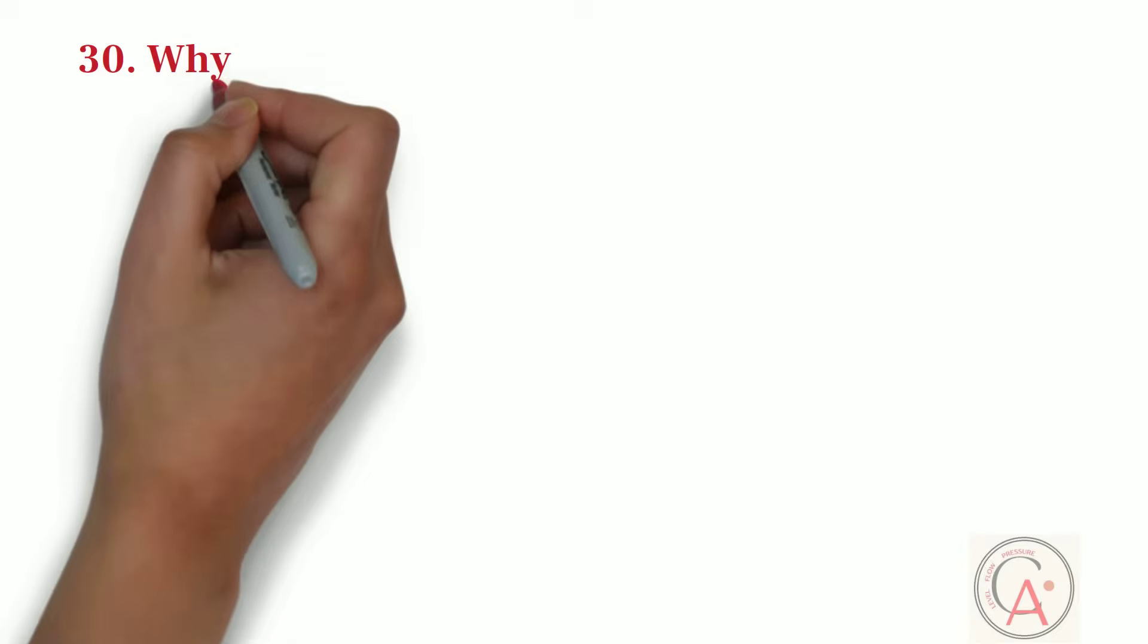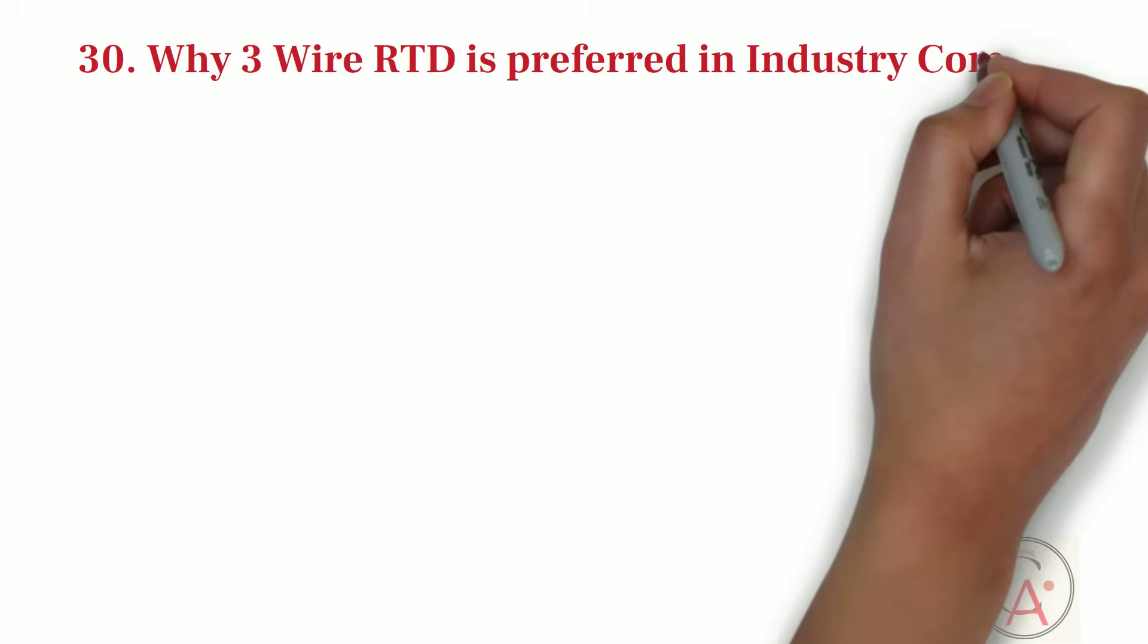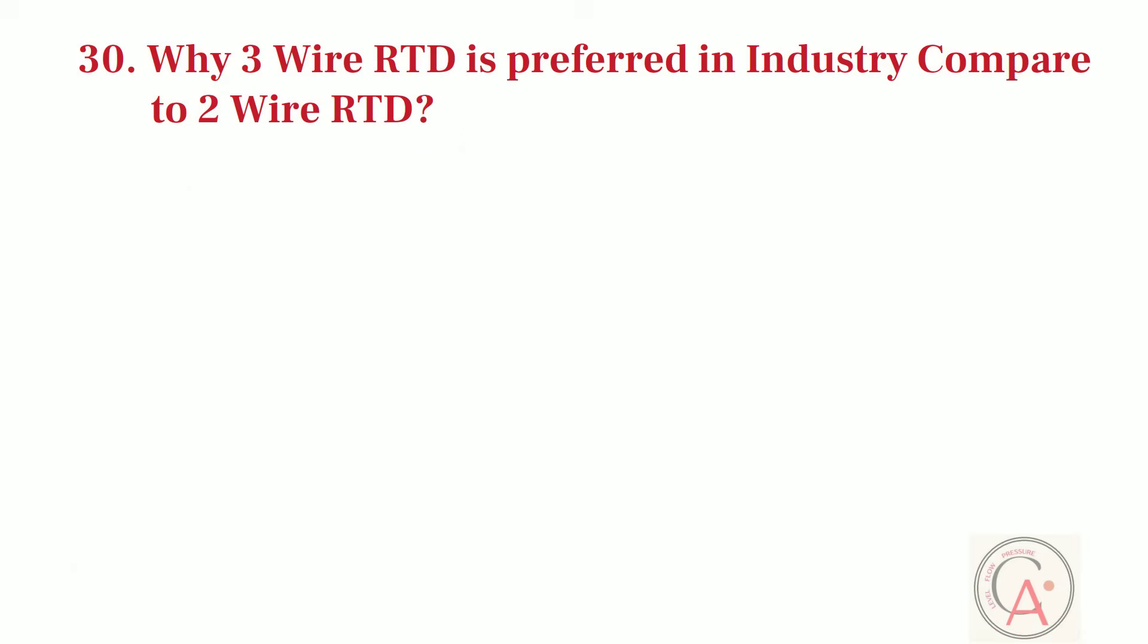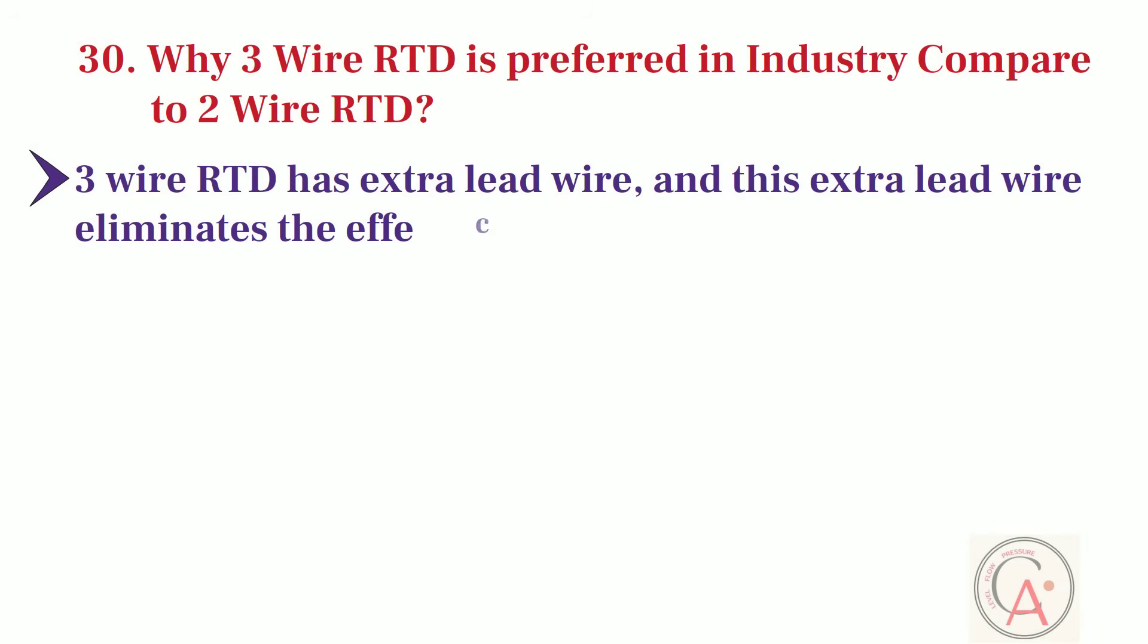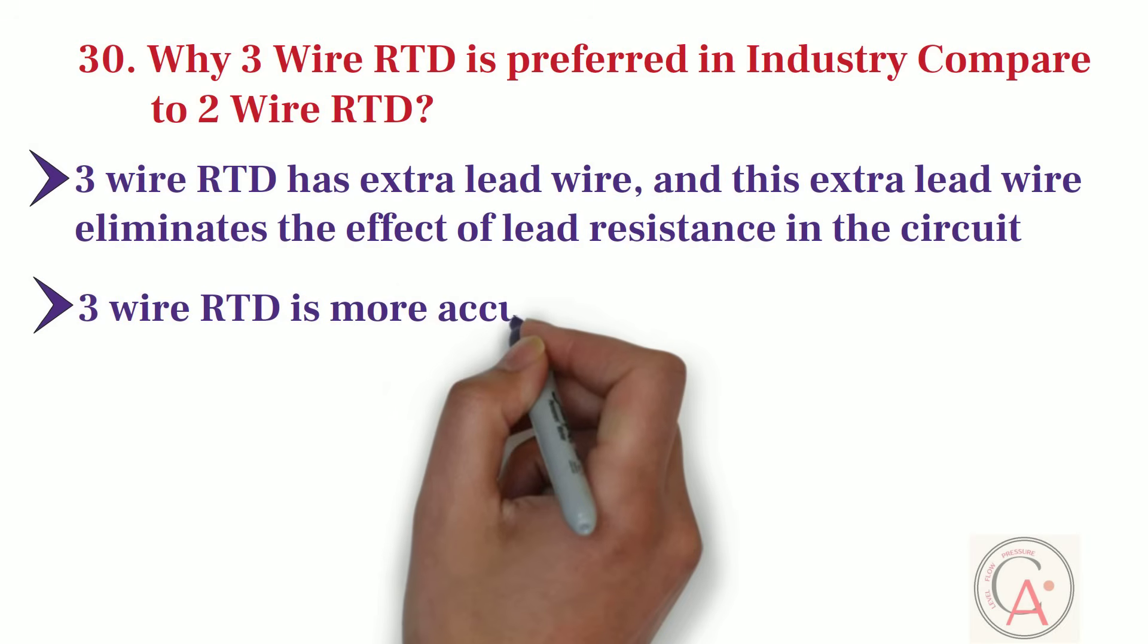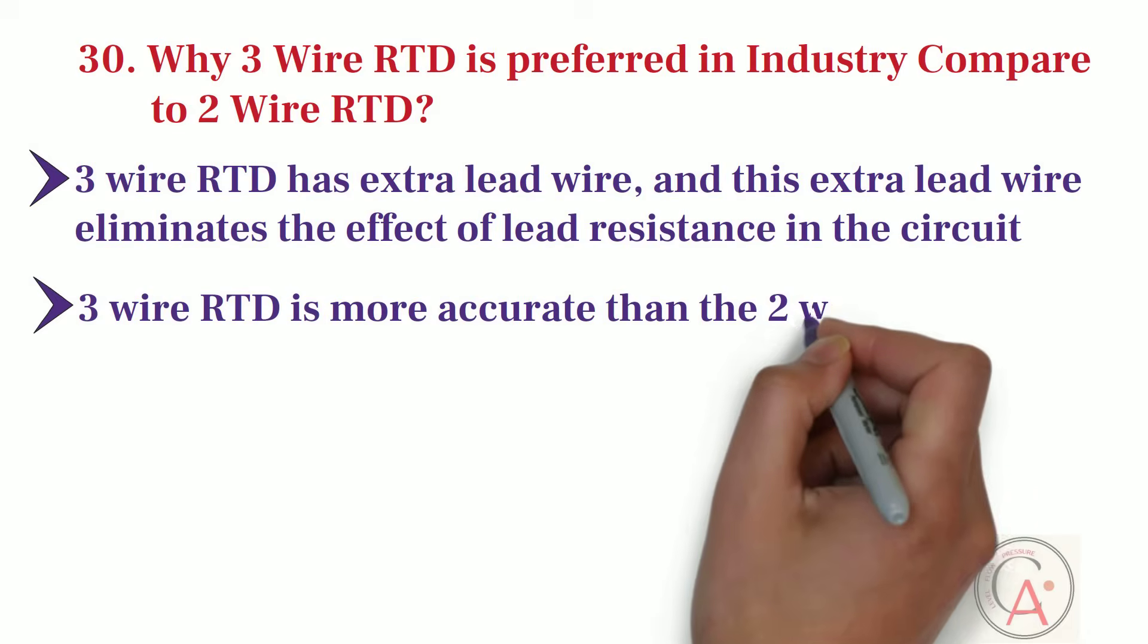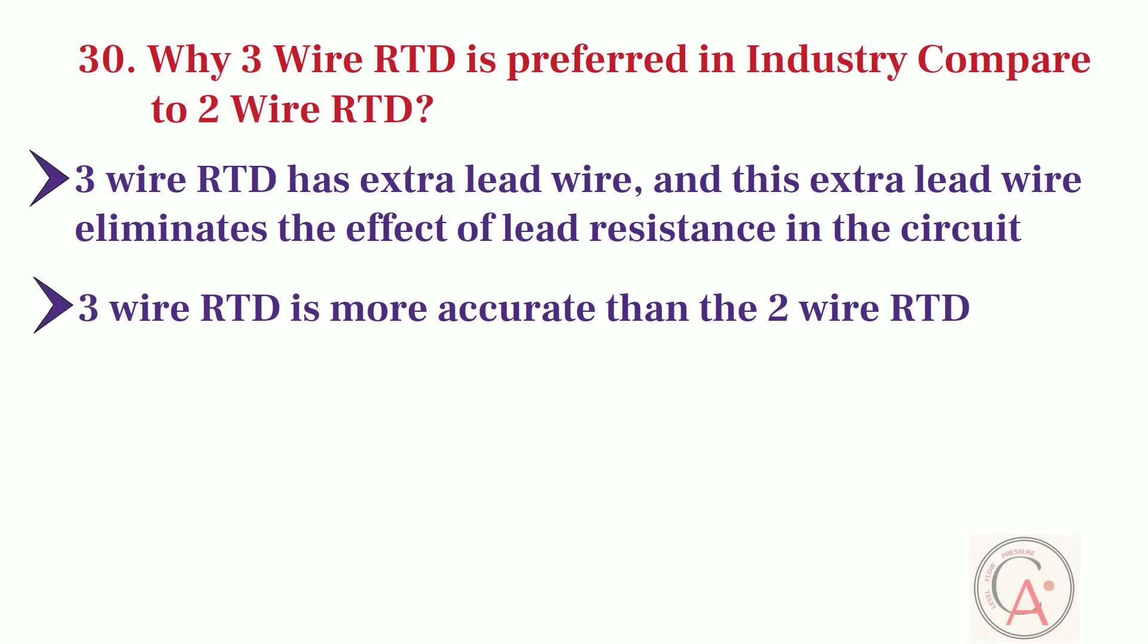Last question is, why three-wire RTD is preferred in industry as compared to two-wire RTD? Three-wire RTD has extra lead wire, and this extra lead wire eliminates the effect of lead resistance in the circuit, which is not possible in two-wire RTD. Because of lead wire compensation feature, three-wire RTD is more accurate than the two-wire RTD. And this is a reason three-wire RTD is preferred in industry compared to two-wire RTD.